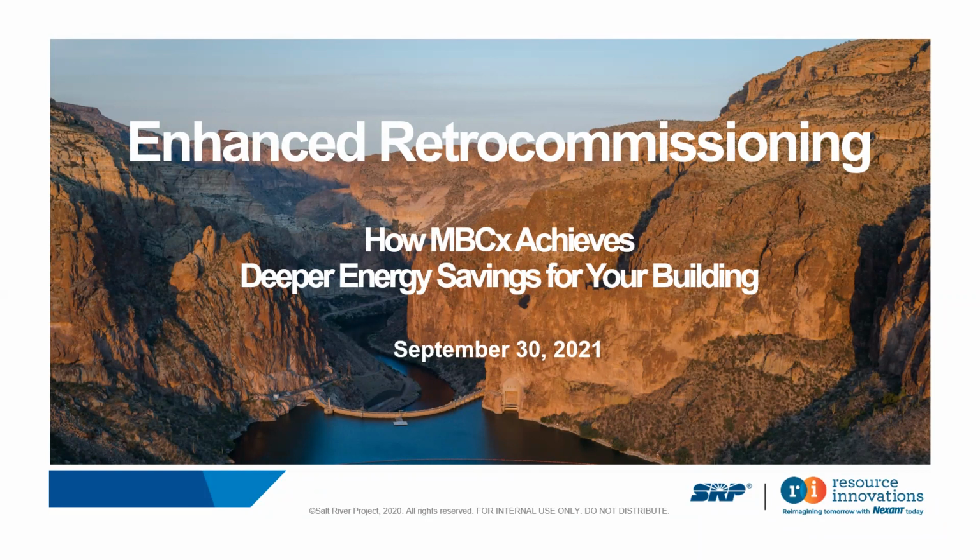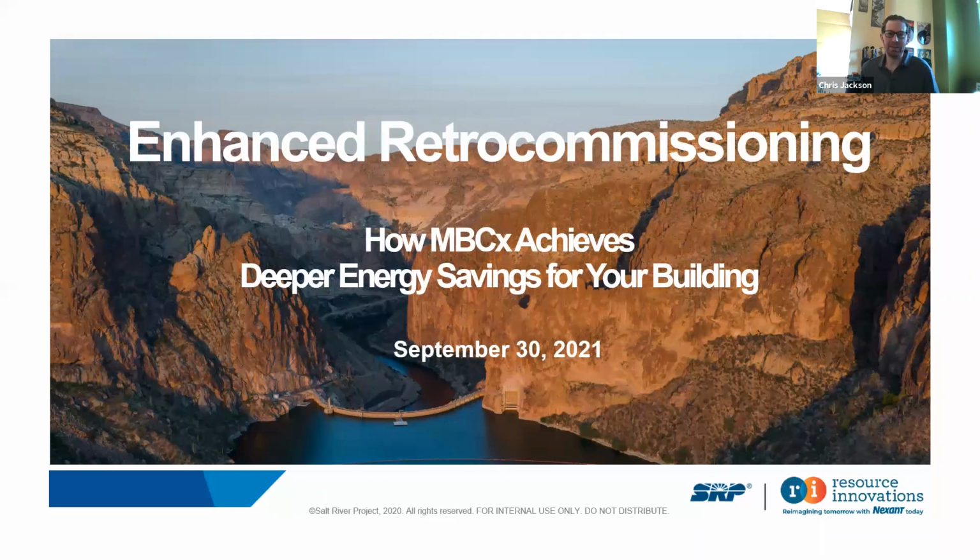I'll take that one. April implied a little bit earlier about preventative maintenance versus reactive maintenance. Going out to fix your failed valves and your failed dampers can save you the time of chasing down hot and cold calls into the future. And that's a huge one. April showed the example of the chiller that was low on refrigerant and equipment wear and tear. You'd much rather have your chiller service technician come in and charge your chiller, prevent surge, and save the life of that equipment than have an unexpected failure. So those are a couple of things where a little bit of time up front can save you time in the long run.